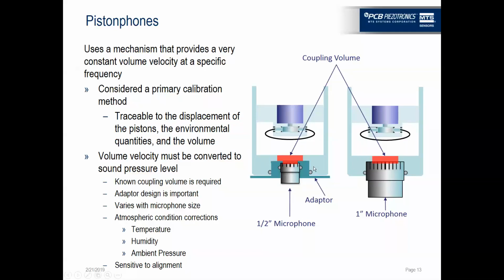It also needs to be known what the adapter is, and what the microphone size is. And then from there, because it's an air volume, in order to convert from volume velocity to pressure, you have to know the temperature, humidity, and ambient pressure in order to be able to do this calibration.